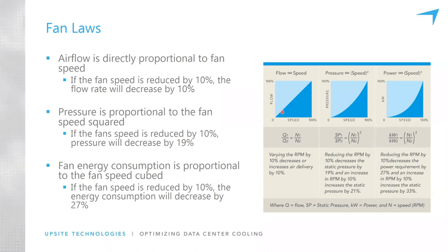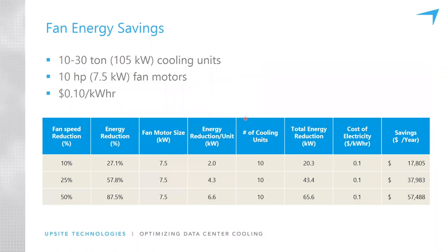So how this plays out is if we have a computer room with 10 30-ton units, 105 kilowatts, by the way, and I really encourage everyone to consider cooling unit capacities in terms of kilowatts and not tons, because it's much easier to compare apples to apples by looking at kilowatts. So we've got 10 105-kilowatt units. Those can typically have a 10 horsepower or a 7.5 kilowatt fan motor. If you're paying 10 cents a kilowatt hour, at a 10%, 25% and 50% fan speed reduction, you end up with annual savings of $17,000, $38,000, and $57,000 respectively.